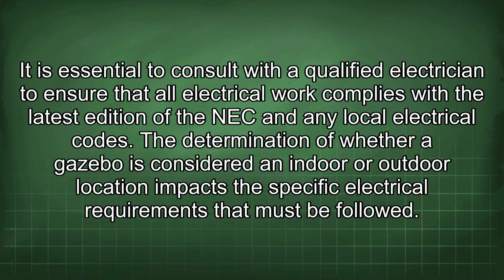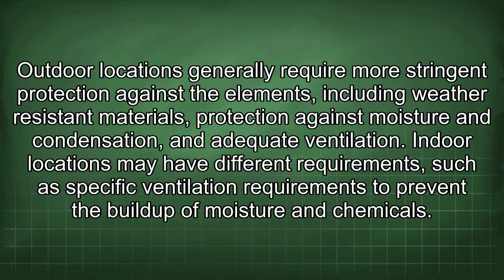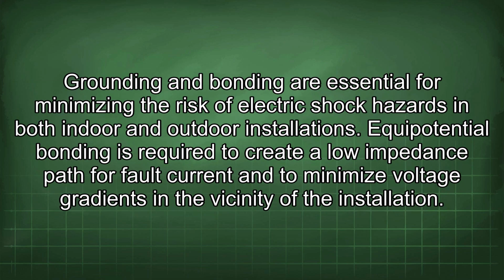The determination of whether a gazebo is considered an indoor or outdoor location impacts the specific electrical requirements that must be followed. Outdoor locations generally require more stringent protection against the elements, including weather-resistant materials, protection against moisture and condensation, and adequate ventilation. Indoor locations may have different requirements, such as specific ventilation requirements to prevent the buildup of moisture and chemicals. Grounding and bonding are essential for minimizing the risk of electric shock hazards in both indoor and outdoor installations. Equipotential bonding is required to create a lower impedance path for fault current and to minimize voltage gradients in the vicinity of the installation.